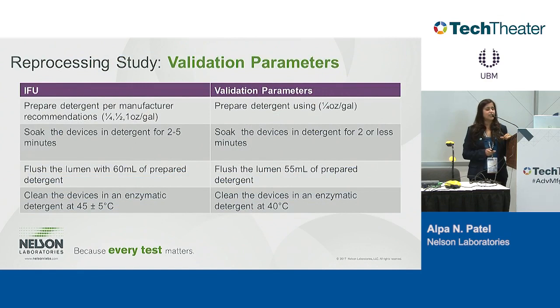Also, when you do validation parameters, how we evaluate is if you have an IFU, the validation is performed with less time, less soak time, less brush time, less flush time. So it will be less than what the IFU specifies for reprocessing.